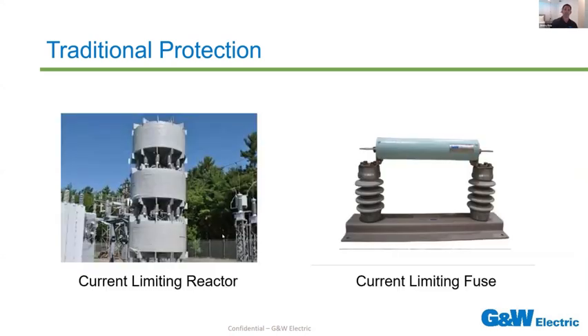Next slide, please. And this one slide is to just give you perspective into the two different traditional solutions that I've just presented. To the left, a current limiting reactor. As you can see, it could be a few stories high. That's in a substation. Versus the current limiting fuse that could be in the realm of 2 feet wide by 5 feet, right? A much more compact solution.